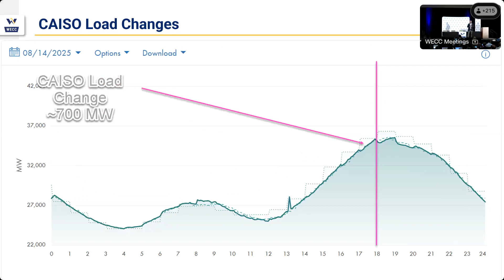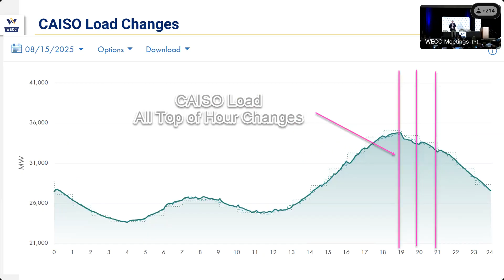We tied it to load changes within the Cal ISO — top of hour load changes within the Cal ISO of significant magnitude to move frequency. So this is one day in August that we saw, another day in August, about a 700 megawatt load change instantaneously, and a couple days later, 3 load changes in 3 different hours, all top of the hour.